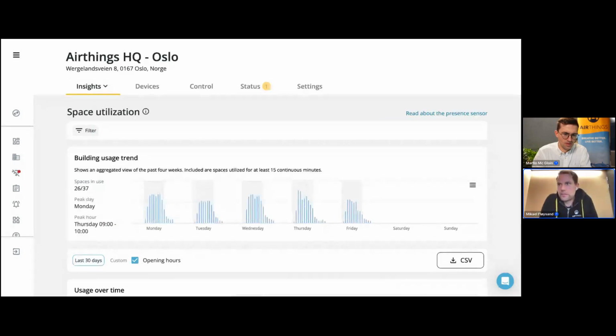So this can also be very useful for ventilation optimization, because one thing is how much air is being replaced, but another thing is when this is going on. So typically, a calendar-based system might start at 6 a.m. and then run until 6 p.m., 12 hours a day. But usually that's not necessary because people won't be arriving that early.